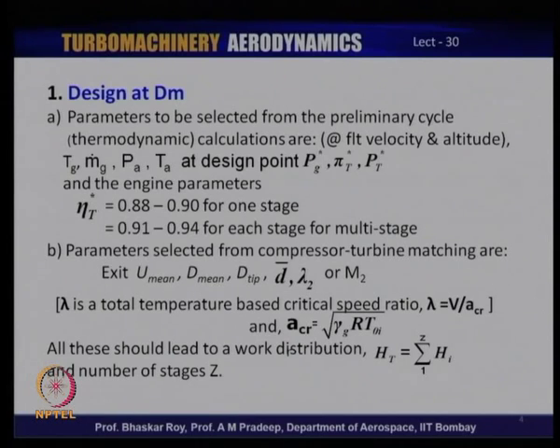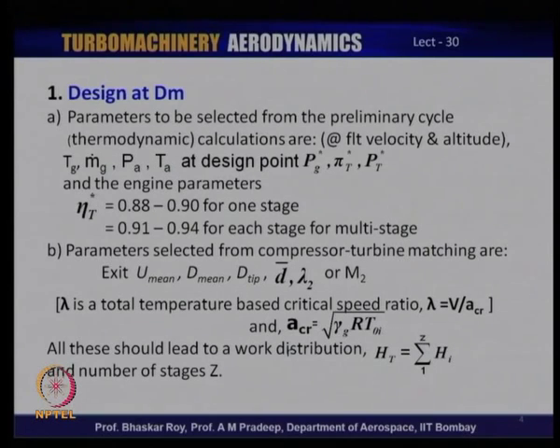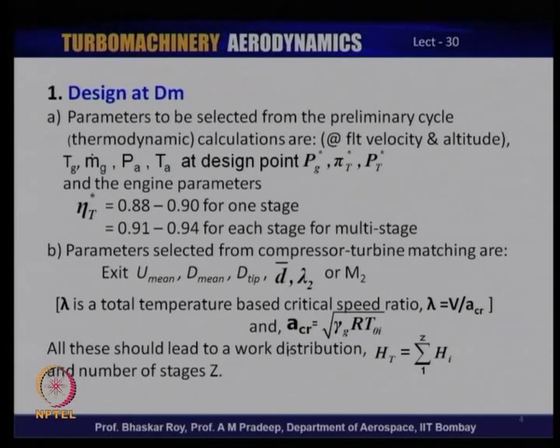The efficiency values used here are ball-park figures to start the design process. For a single-stage turbine, efficiency of the order of 88 to 90 percent is often possible, likely for a high-pressure ratio axial flow turbine. For a multi-stage turbine, individual stage efficiencies are on the higher side, with the overall multi-stage efficiency around 90 percent, while individual stage efficiencies nowadays could be as high as 94 percent.